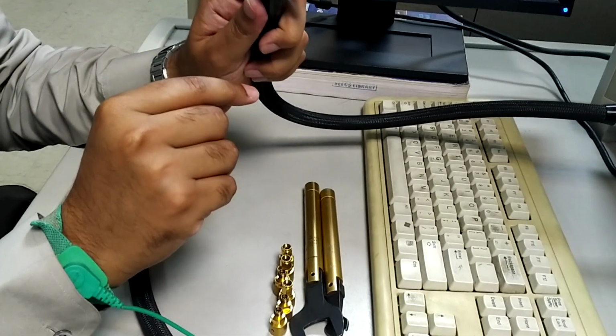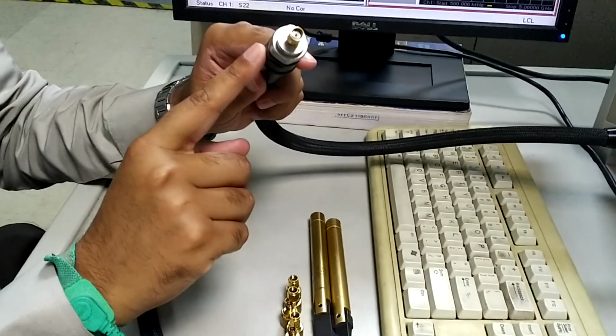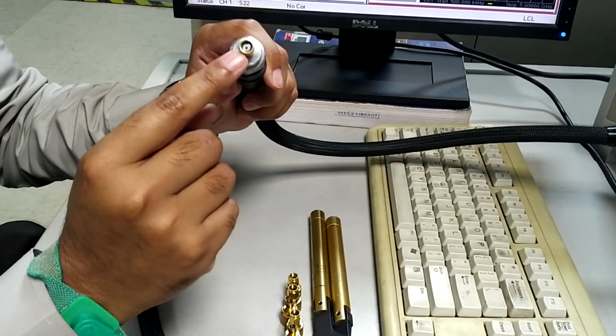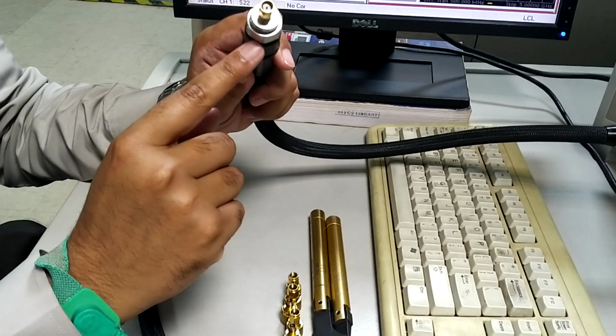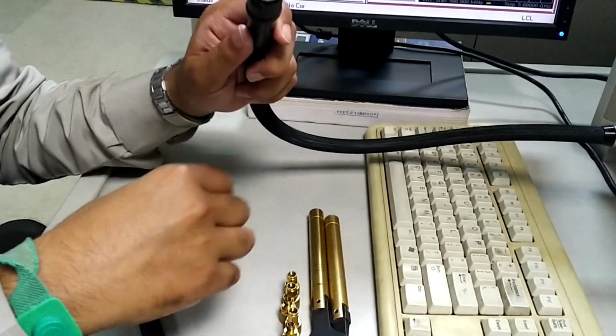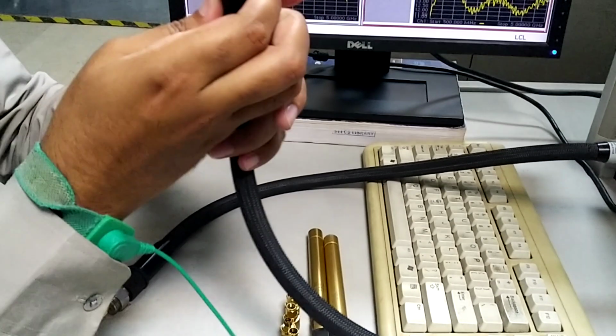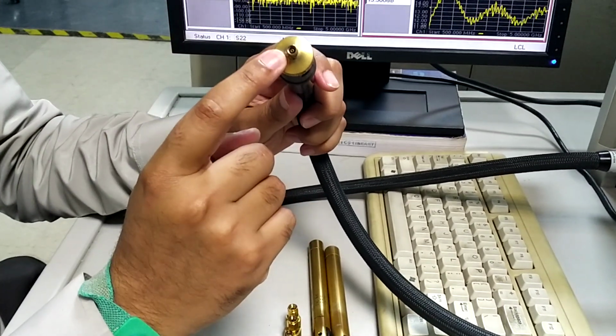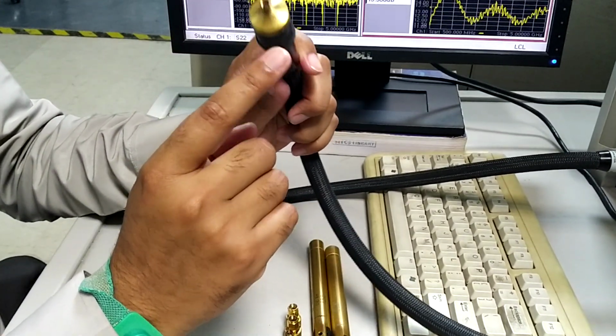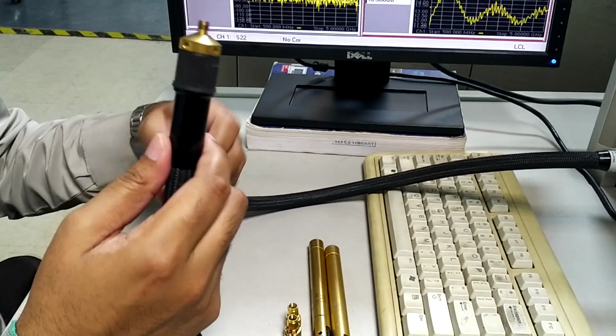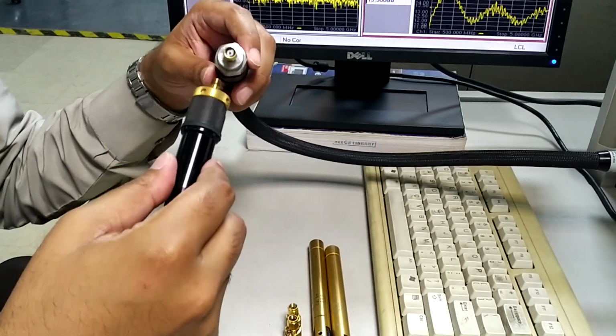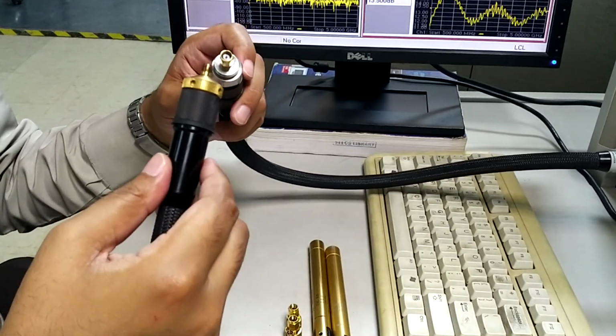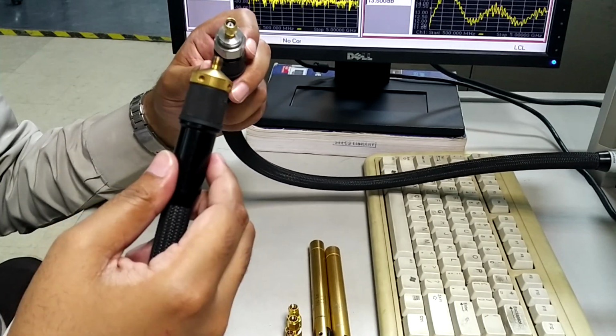So this is the cable that is connected to port 1, and it has a male standard. You can see the pin inside. This is a male standard cable, and this is the cable that is connected to port 2, and you can see this is a female standard as there is no pin available. The benefit of having cables with different genders is that I can perform a direct through, which means I can perform a zero length through, as I told you in the class.